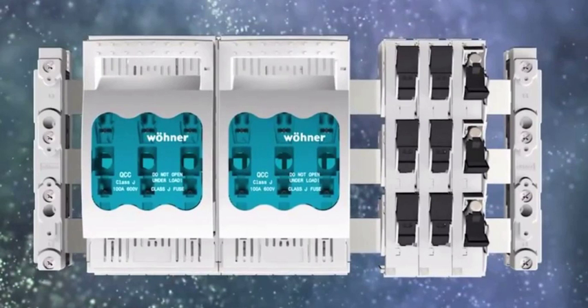in an electrical enclosure. Busbar system is subject to safety standards for design and installation along with electrical enclosure according to IEC 61439-1 and varies by locality, country, or region. And the system depends on allowable busbar types and sizes, which vary according to operating voltage and current carrying capacity.